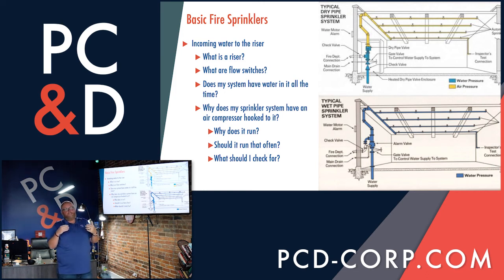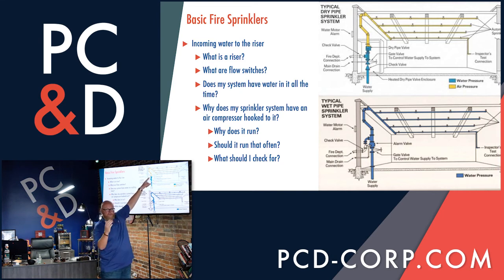But a very general approach to this is, if you've got water pressure coming from the bottom, and we'll just pick a number, at 100, you have to have what? You have to have more than 100 to hold it back, right? So that is how your dry system stays dry. Your air compressor runs and pumps air into your dry side. That air holds this flapper valve closed. The flapper valve is closed. You've got literally water on one side, ready to go, and air on the other side holding the flapper valve down.